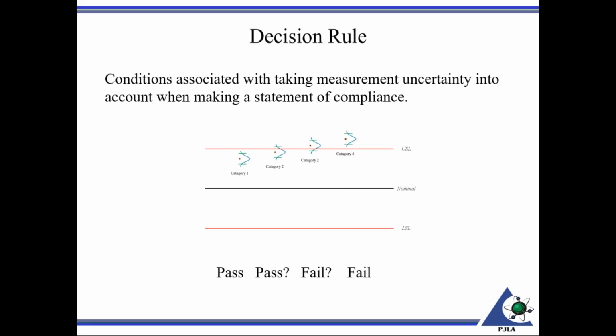Category 2, the value actually passes. However, the uncertainty creeps over the spec limit. So it may not be a pass after all if you take uncertainty into account. Or in the other case, category 3, it could barely fail, but it may not fail when you consider uncertainty. And category 4, that's a clear failure. So the value itself with the uncertainty incorporated into it is above that spec limit. So again, the decision rule is how you take measurement uncertainty into account. There are various means of doing that.